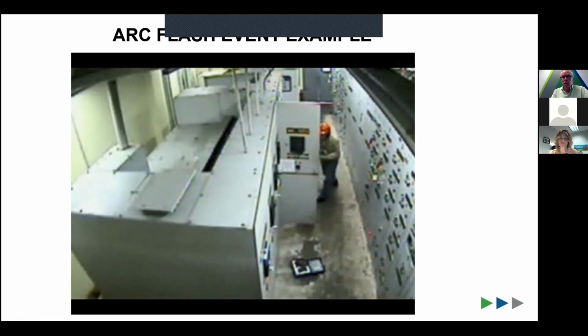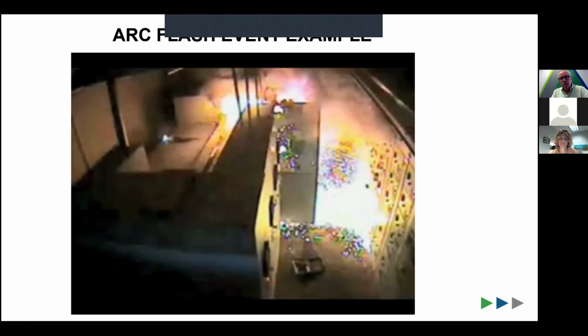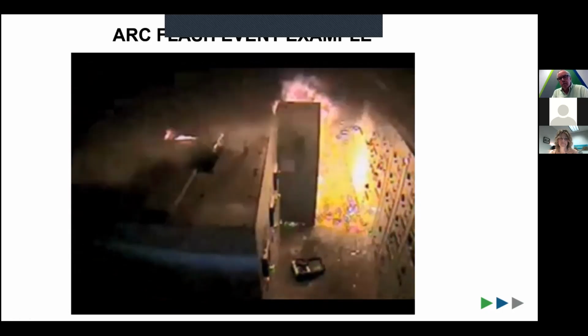An important item that many, if not most, employers don't think about is emergency lighting in substation areas. So the question that comes to mind looking at that video is, okay, how did those guys escape? How did they crawl out of that room that got filled with toxic fumes? So if they didn't get burned, there's no natural light in that room - so how did they escape?